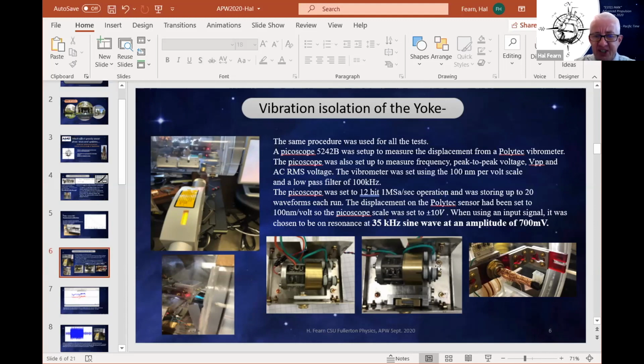So we wanted to see if this was actually better at vibration isolation than the L bracket. So one of the tests that I ran was to shine the vibrometer here directly at the Faraday cage, not at the beam or the yoke, but directly at the Faraday cage, and see what difference it would make if I run the device with the L bracket or this interesting sliding L bracket here. Sledge. Yes, he calls it a sledge. Fine, it's a sledge. It doesn't look anything like a sledge to me, but I guess it's got two runners. It's a sledge. All right, fine. So let's see what difference it made.